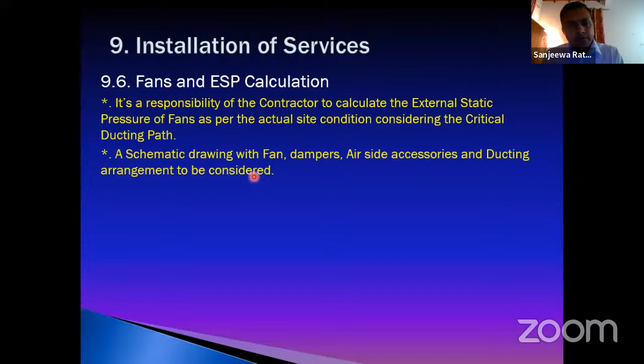If I elaborate on all the components here, this schematic diagram shows the fresh air louver, then the reducers, a sound attenuator, a flexible connection, and the fan. Then there are also reducers, bends and branch pipes, but only the critical path is considered. The table shown is the method to calculate the ESP of each part, and at last they find the ESP of the fan as 130 Pascal. I just want to show this, not to calculate here, but this is a good practice. As a contractor, it's not just to follow the engineer's instruction.